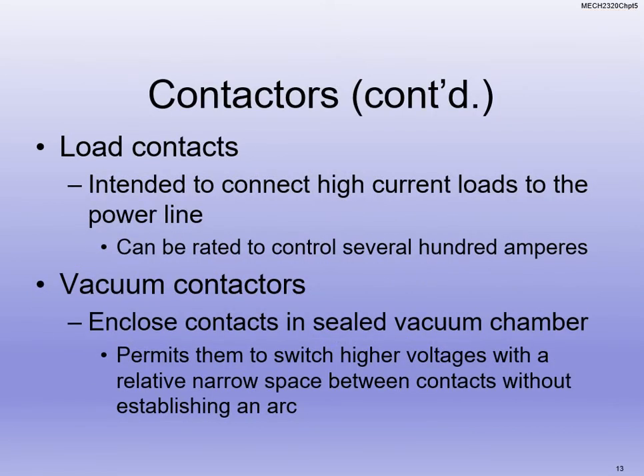With load contacts, we intend to connect higher current loads to a power line using a smaller control voltage. It's the same concept as when we used Arduino boards to do blinking lights — we ran a separate relay because our lights ran on 12 volts and our controls on 5 volts from the Arduino board. So we use a smaller control voltage, like 24 volts from our PLC, to control higher voltage loads.